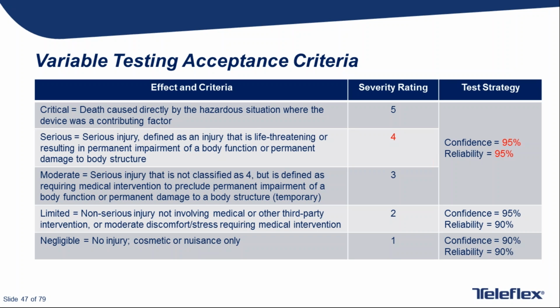So when possible, challenge your engineers if they think that something has to be an attribute test. Variable data should be collected. It provides more information about the statistical distribution. And if challenged, engineers can be very innovative with testing in order to turn attributes into variables. So it's appropriate to challenge why attribute data is necessary for any particular case. Test methods can be designed and validated, and I'm sure you have very capable engineers that can do that when challenged.